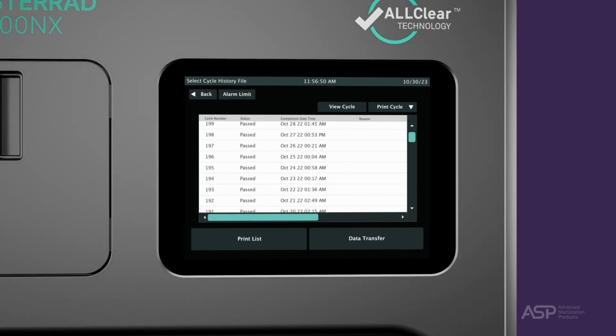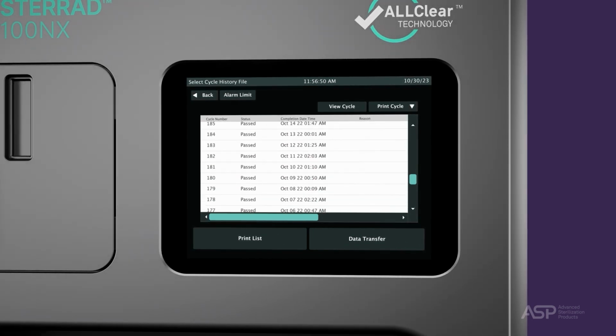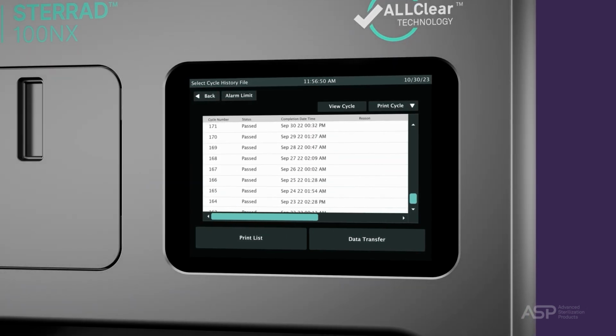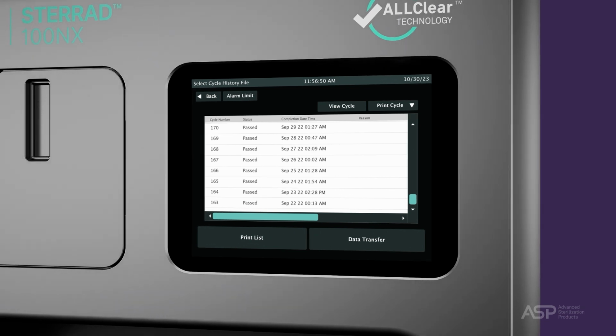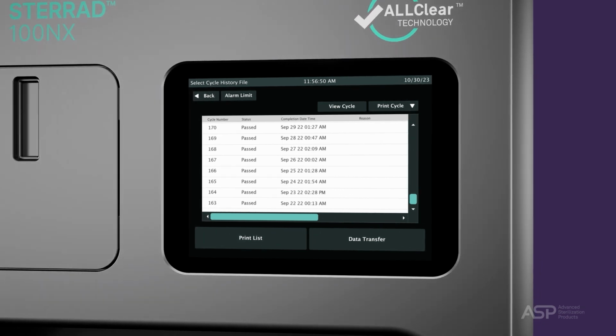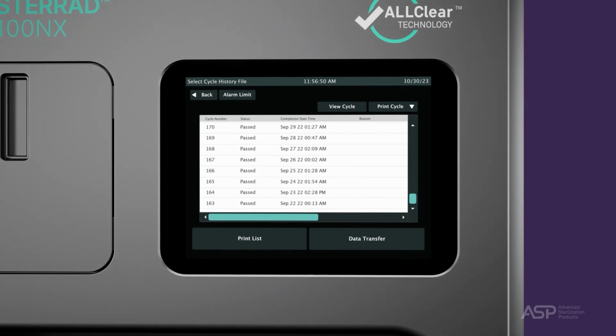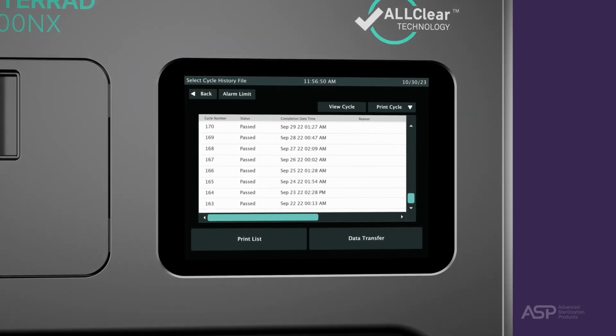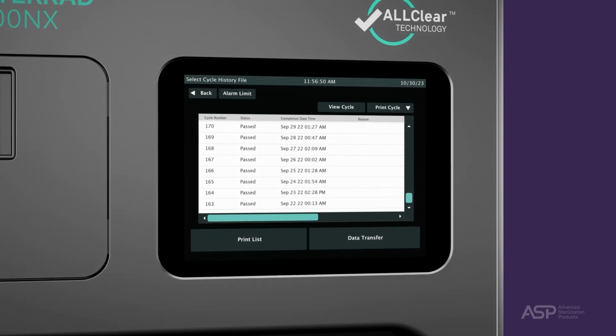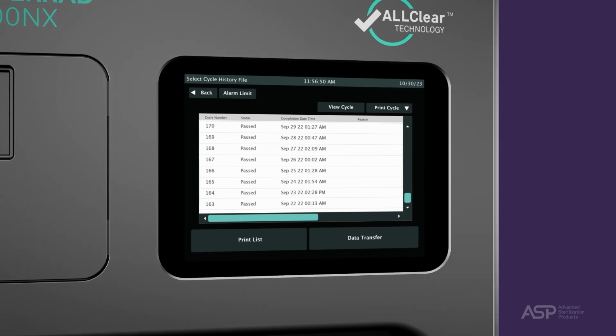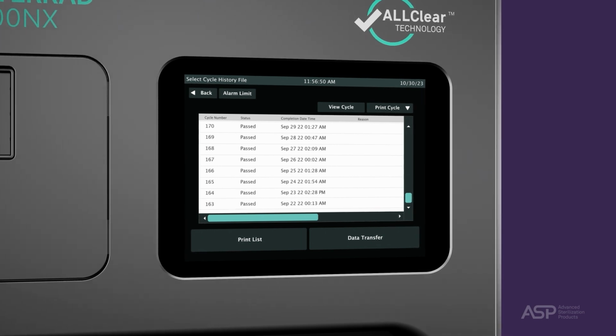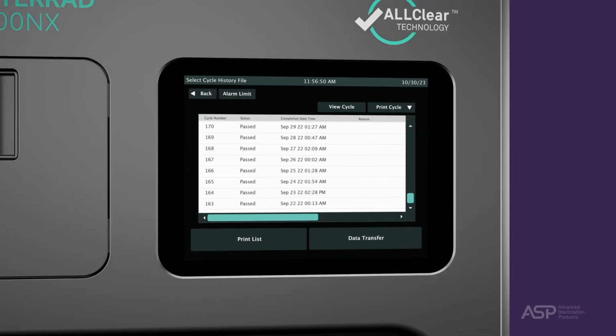Cycle history data is stored in the sterilizer's memory, which holds the most recent 200 cycles. After 200 cycles are completed, the oldest cycle history record is overwritten with new data from the 201st cycle. When you see the message "Memory card full," it is an indication that the cycle history must be downloaded, or you can select OK to continue with overriding the stored data.